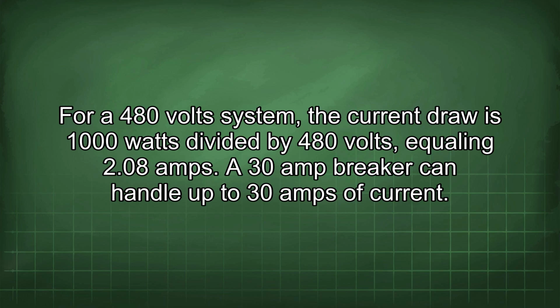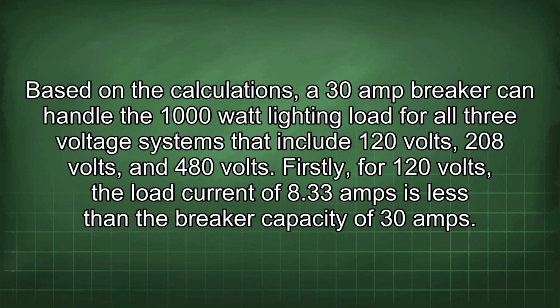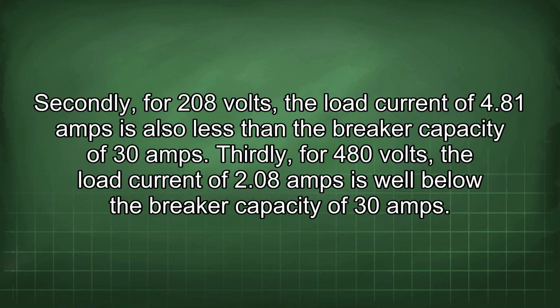A 30 amp breaker can handle up to 30 amps of current. Based on the calculations, a 30 amp breaker can handle the 1000 watt lighting load for all 3 voltage systems that include 120 volts, 208 volts, and 480 volts. Firstly, for 120 volts, the load current of 8.33 amps is less than the breaker capacity of 30 amps. Secondly, for 208 volts, the load current of 4.81 amps is also less than the breaker capacity of 30 amps. Thirdly, for 480 volts, the load current of 2.08 amps is well below the breaker capacity of 30 amps.